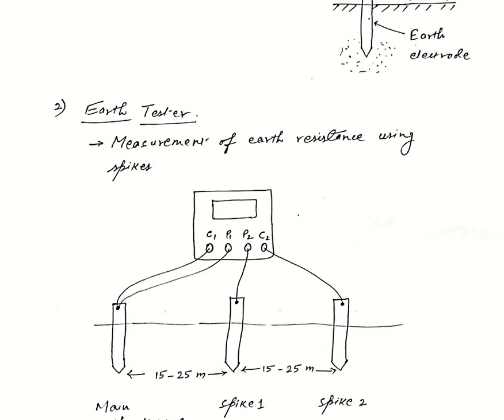The earth tester has four terminals on it: C1, P1, P2, and C2. C1 and P1 are shorted as you can see here, these two are shorted and connected to the earth electrode for which we want to measure the earth resistance. P2 is connected to the first spike S1 and C2 is connected to second spike S2.